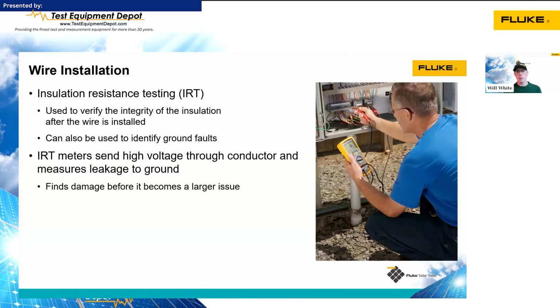Essentially, what an insulation resistance tester is doing is it's sending a high voltage, low current through the conductor. It's essentially charging that conductor up and then looking for current leaking to ground. The important thing to know when you're doing this is that the wire can't be connected to any other circuits or any electronic equipment because the test won't function properly. So it's really a good idea to do insulation resistance testing at installation after the wire is installed in the conduit, but before it's terminated on any terminals like at an inverter or a combiner box.